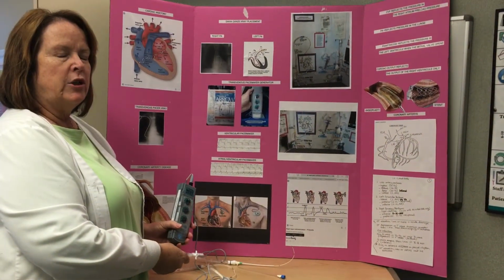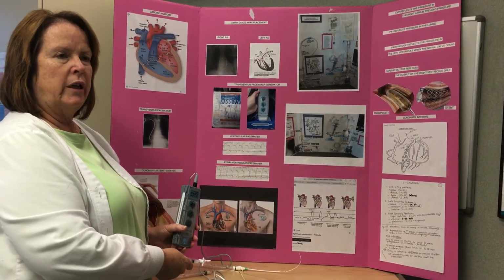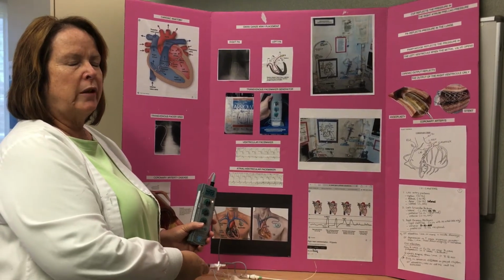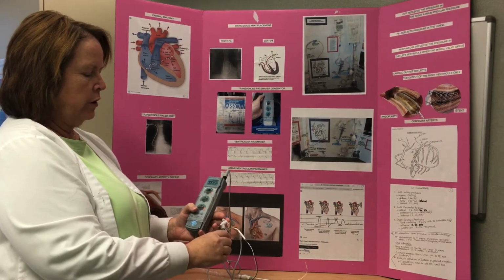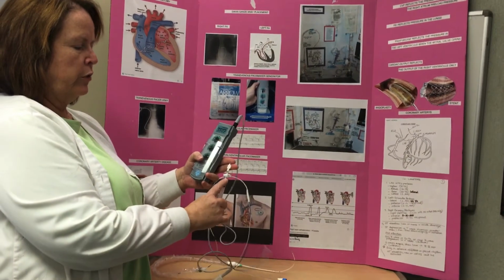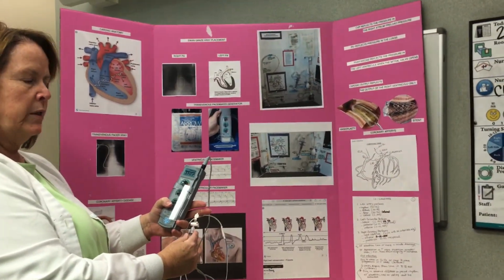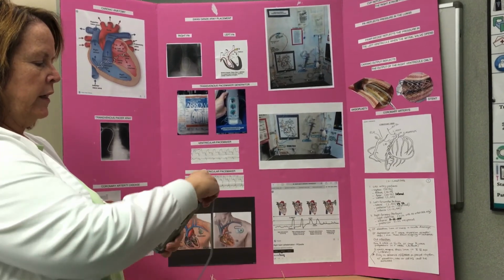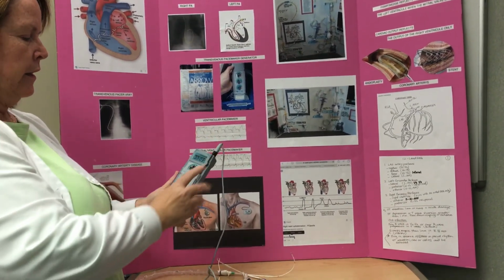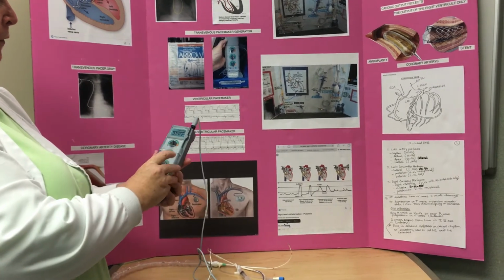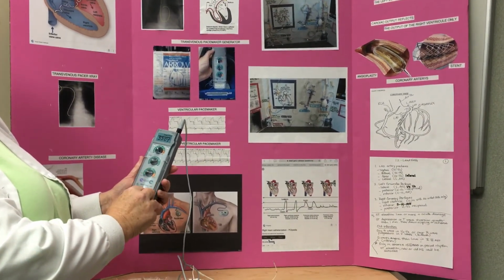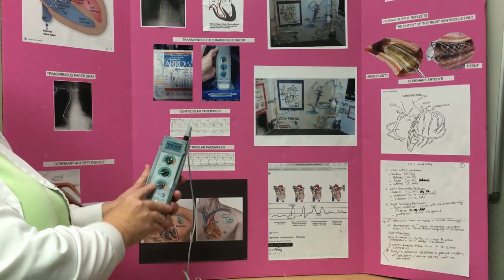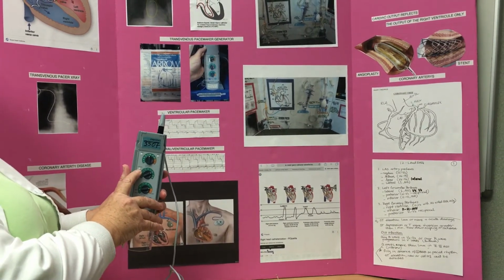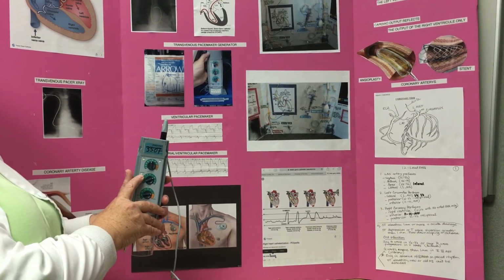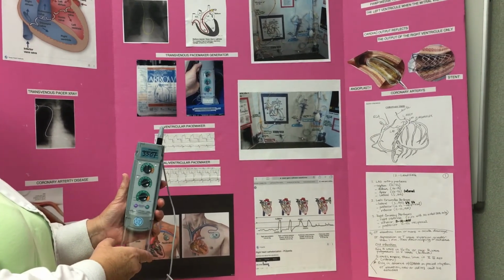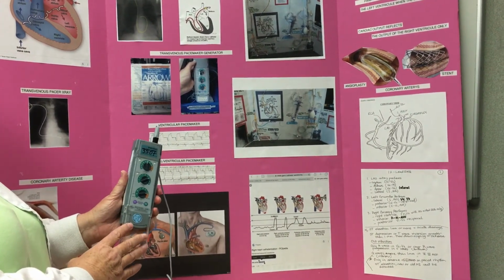If you receive a patient who has a transvenous pacemaker already placed, what is your responsibility? You need to make sure that the balloon is always down, so your syringe should have air in it and be in the locked position. You need to make sure that it's held up nice and tight, and that the pacemaker is on. If the pacemaker battery is running low, there's a light here that says low battery. So you need to make sure your battery is always working on your patient, because their life could be dependent upon it.